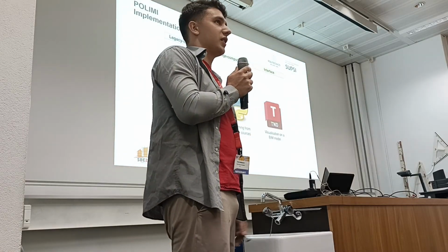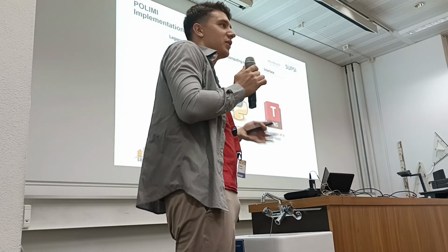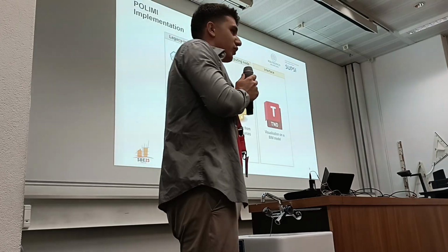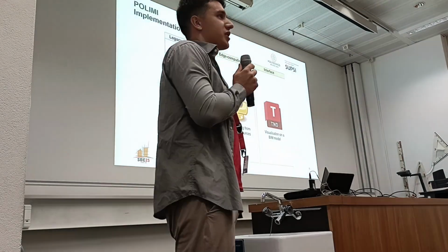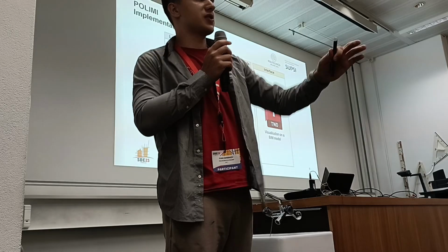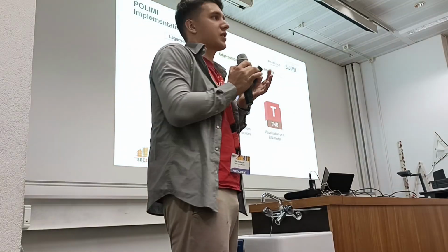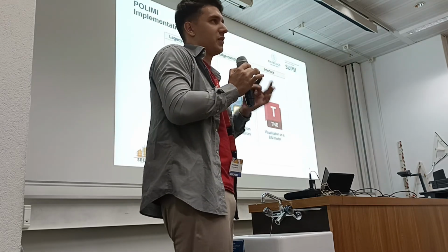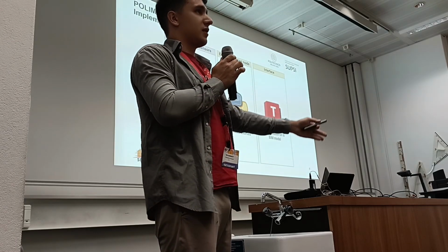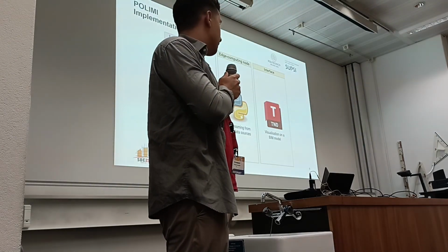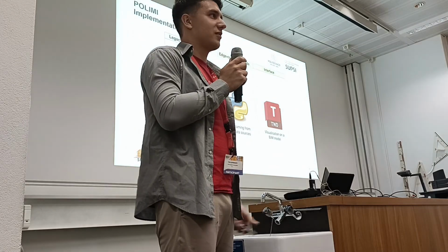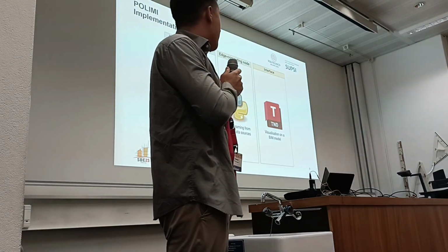The problem was that since all the sensors were installed by different people going for different goals, the data sources were heterogeneous, super variable. It was not just one Influx database, it was everything. So we decided to pull each of the sensors and group it in an Influx database together with Postgres, for data that is not time series. Then we reformatted this data in a format supported by Autodesk proprietary software called Tandem, which is freemium, let's say, and visualized it there.